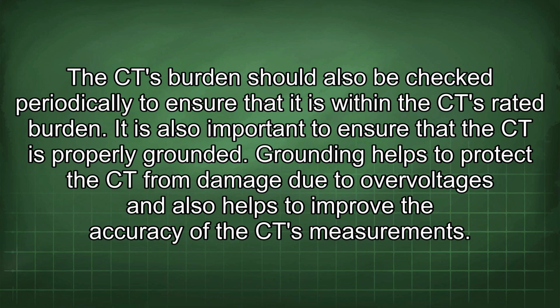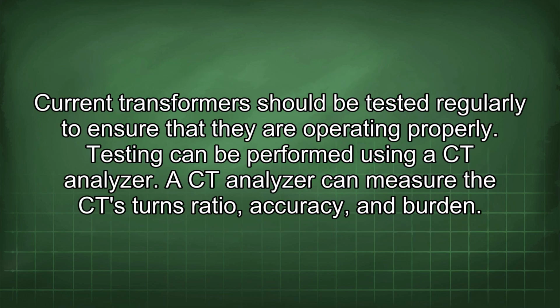It is also important to ensure that the CT is properly grounded. Grounding helps to protect the CT from damage due to overvoltages and also helps to improve the accuracy of the CT measurements. Current transformers should be tested regularly to ensure that they are operating properly.